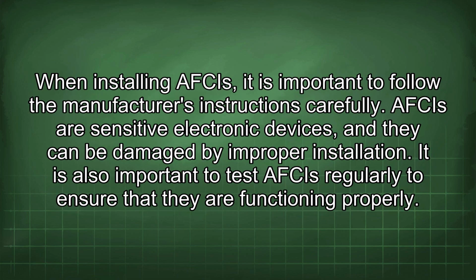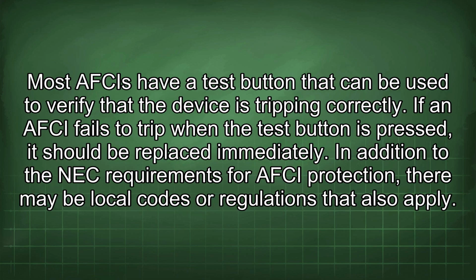When installing AFCIs, it is important to follow the manufacturer's instructions carefully. AFCIs are sensitive electronic devices, and they can be damaged by improper installation. It is also important to test AFCIs regularly to ensure that they are functioning properly. Most AFCIs have a test button that can be used to verify that the device is tripping correctly. If an AFCI fails to trip when the test button is pressed, it should be replaced immediately.